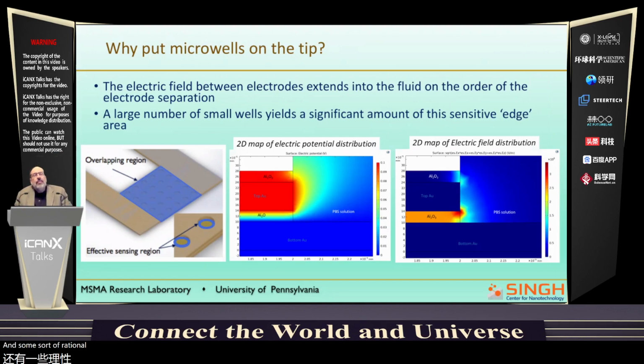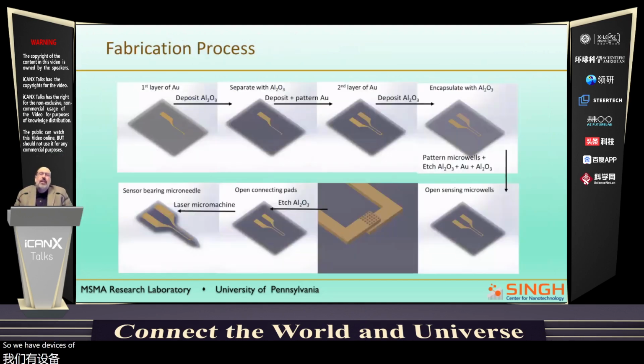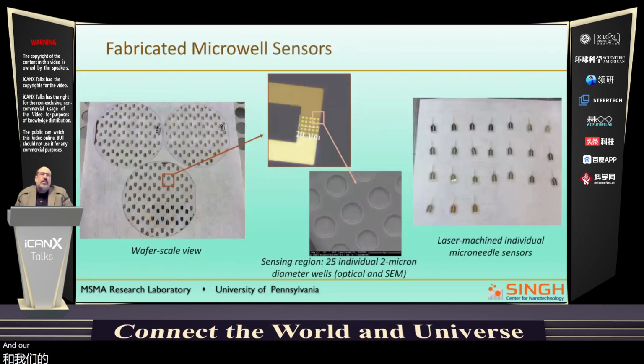We can fabricate these devices using typical microfabrication technology. We typically use a glass substrate, deposit and pattern our multilayers of gold, alumina, and gold. Then we pattern the microwell array in the overlapping region between the two electrodes, open up connecting pads, and when we're finished, we use laser micromachining to dice out individual microneedles that have the sensing region at the tip. So very straightforward MEMS fabrication. And here's a sequence of how this is done.